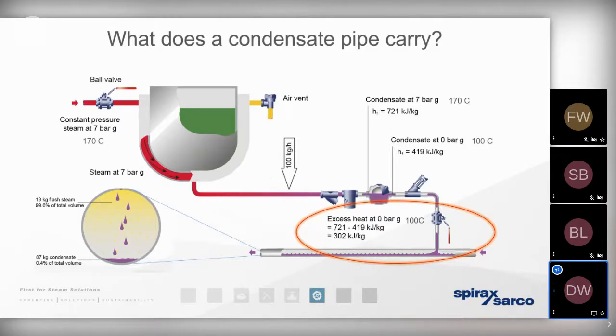But the problem is, if we've got a significant fall in pressure downstream of the steam trap, by referring to the steam tables, we understand that, for example, a fall in pressure from 7-bar gauge to 0-bar gauge means that the sensible heat has got to fall from 721 kilojoules to 419 kilojoules. So how can that condensate give up that energy in such a small distance? The answer, well, a certain mass or a certain percentage of that liquid condensate is going to change state back to steam again. We call that flash steam.